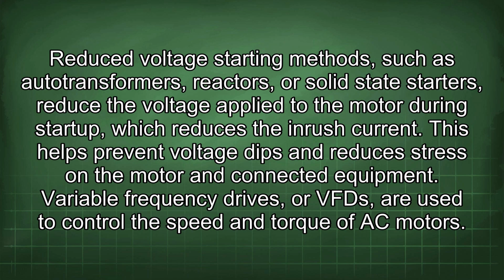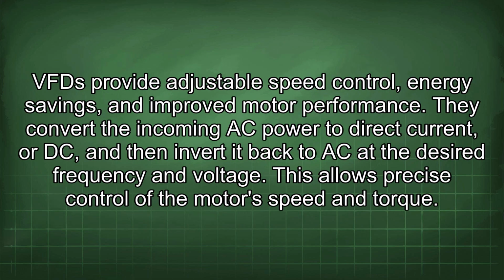Variable frequency drives, or VFDs, are used to control the speed and torque of AC motors. VFDs provide adjustable speed control, energy savings, and improved motor performance. They convert the incoming AC power to direct current, or DC, and then invert it back to AC at the desired frequency and voltage. This allows precise control of the motor speed and torque.